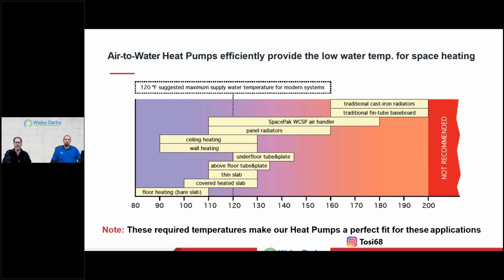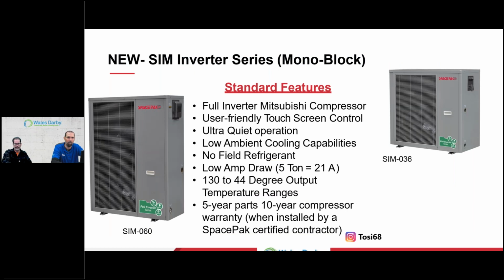So just to reiterate what this slide is showing you: it's water temperatures for having that 120 degree water available. What are my options for emitters? There are quite a few. Redundancy might come into play, having more than one source, having something carry a majority of our heating season using lower water temperatures. Radiant, if you're in the radiant business, which has been re-energized here on Long Island for sure, why not do 120 degree water? We asked earlier what water temperatures you could use for radiant, and I have a slide later, a bit offset to the conversation, but you'll see it again.